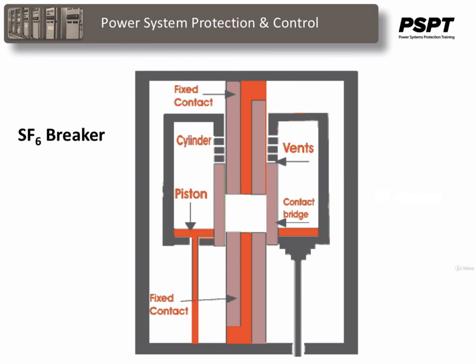The working of an SF6 circuit breaker is a little bit different in modern times. Innovation of puffer type designs makes the operation of the SF6 circuit breaker much easier. In the puffer type design, the arc energy is utilized to develop pressure in the arcing chamber for arc quenching.